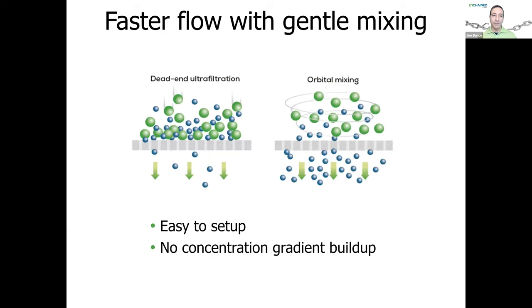We often get asked why we mix. Dead-end ultrafiltration will concentrate your protein at the membrane surface, eventually slowing down flow, potentially fouling your membrane, and potentially impacting protein quality. With orbital mixing, we keep the solution uniform — very similar to a TFF process — which allows faster flow through the membrane, faster exchange, and better protein quality at the end.